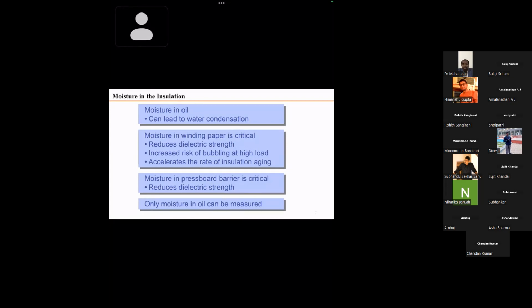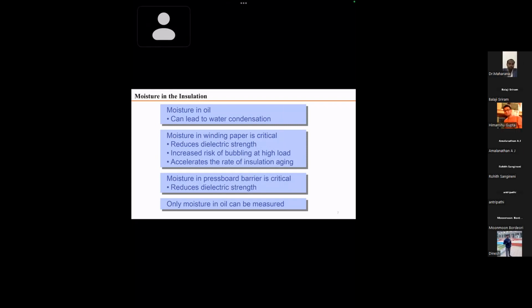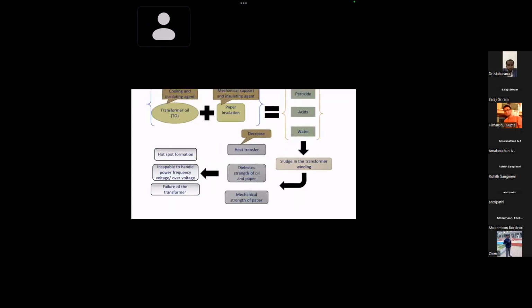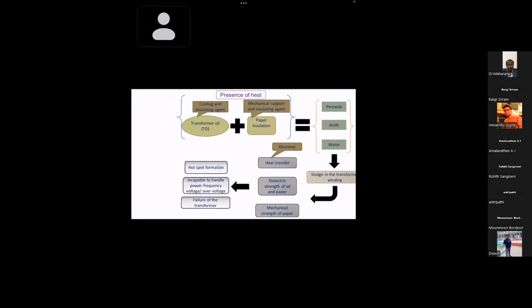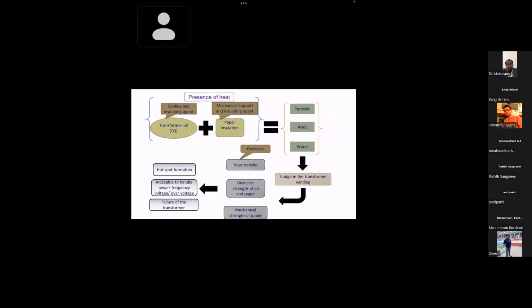Moisture in the pressboard barrier is critical; it reduces the dielectric strength both in the winding as well as in the oil. Moisture in oil can be measured. As I told you on the previous slide, only the moisture in the oil can be measured. So that is the measure we take forward, so that we can check, if this moisture is present in the oil, what the further issues will be. Broadly, a transformer is an agent that maintains stable insulation as well as the cooling.